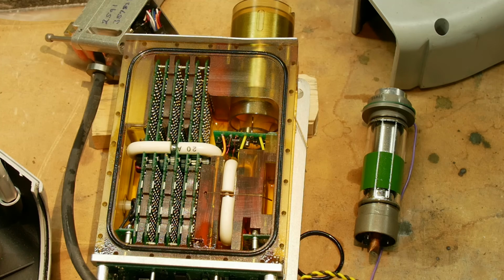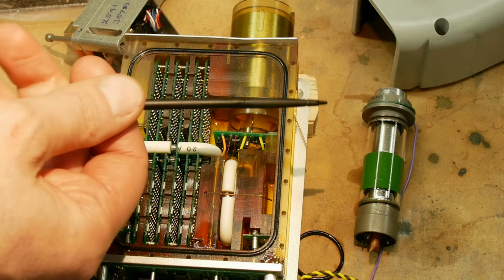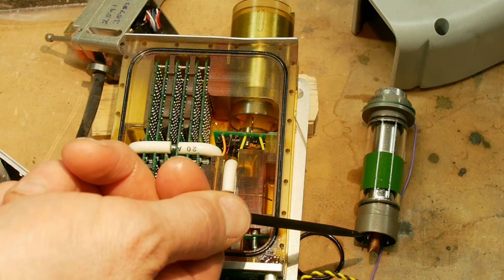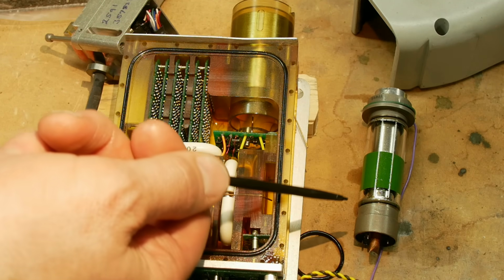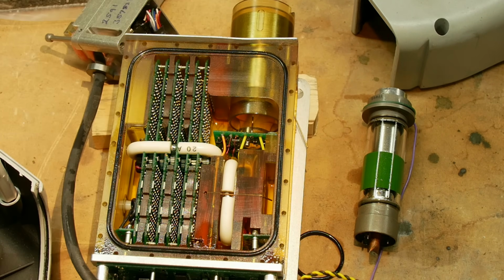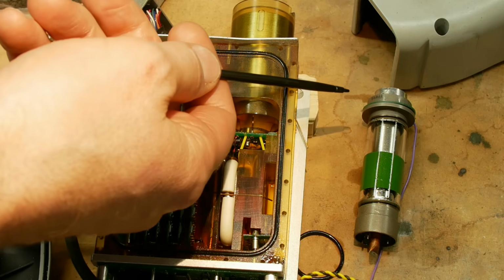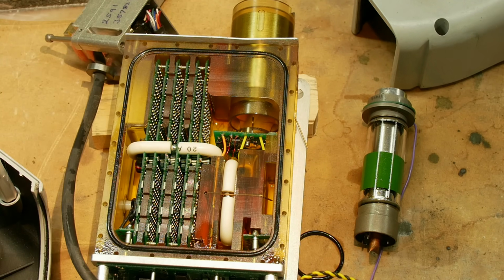Another strange design principle is that it actually is a negative 40 kilovolt supply. So typically, if you want to do an X-ray tube, the way that you make this work is you have to put a filament voltage on the bottom, and you would make this 0 volts, and then you would put plus 40 kilovolts over here, the anode. And the reason you'd want to do that is because you need to control the voltage going into the filament to control how much emission current you get. So the way that you operate an X-ray tube is to just put 40 kilovolts on it, and then measure how much current is going into the anode, and then raise the temperature of the filament until you get the emission current that you want.